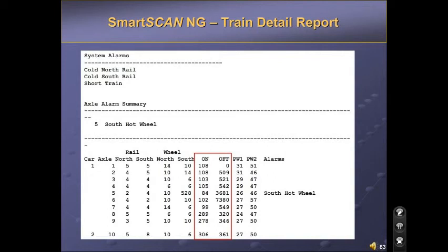If there is a long on time, then one transducer pulsed and the second transducer missed. If the train direction is northbound, it should cross transducer TO1 first. A long on time indicates that a pulse was missed on TO2. If the report shows a number of trains with this miscount, then adjusting the loading on TO2 would be in order. The same would be true on a southbound train. It would cross TO2 first and may indicate an adjustment on TO1 is necessary. If an adjustment is necessary, jumpers J201 and J202 on the interface are the locations of the transducer's loading circuits. Increasing the jumper setting will increase the sensitivity of the transducer, and decreasing will reduce the transducer sensitivity.